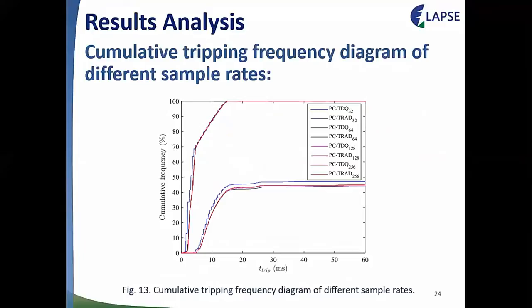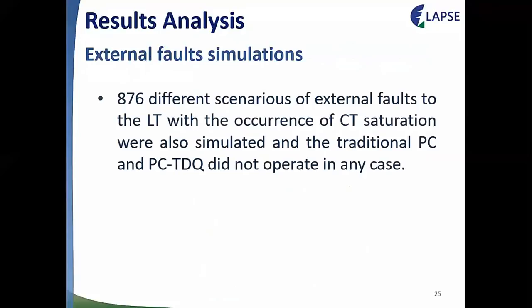The simulations were carried out with a sampling rate of 256 samples per cycle; however, other rates can be used. To demonstrate this, the same cases were simulated with emulation of different sampling rates: 32, 64, 128, and 256 samples per cycle. The results show that different sampling rates can indeed be applied. Finally, several external fault cases to the transmission line with CT saturation were also simulated, and both the traditional PC and PC-TDQ did not operate in any case, proving their safety.